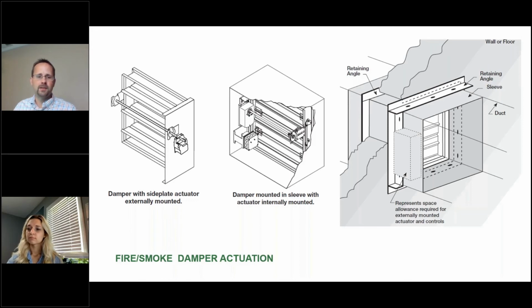There are a lot of different options. You can have an actuator in the airstream if you're in a tight spot, so you just get to that actuator through the access panel. The only problem is that's additional pressure drop on your system. So that's an energy issue. Also, just through the lifetime, having that in the airstream creating a pressure drop is something you don't want to do unless you absolutely have to. And those actuators can be installed in a lot of different places. It's just making sure you coordinate if it has to be installed on the bottom or the left or right, so that it gets installed on the proper side.